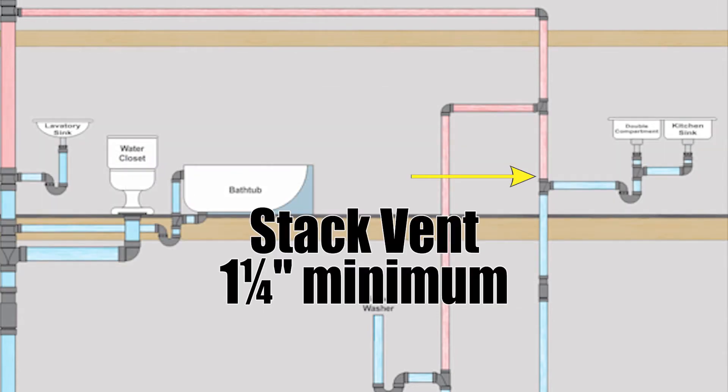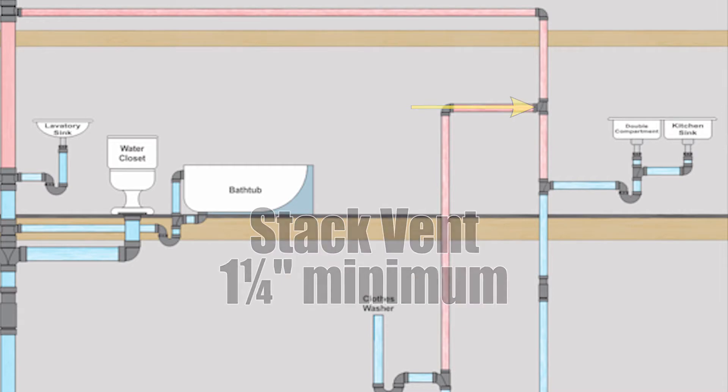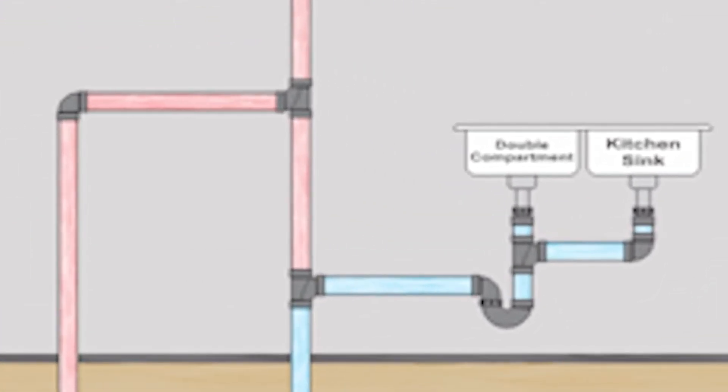Now we'll see that the stack vent goes up and it intersects with the individual vent right there with the TY. There's a couple things we need to talk about right there. The first thing I want to point out is the orientation of the TY. Notice how it looks like it's upside down. Well that's how we put it in for venting because the general flow of air is going up through the terminal which is the part that pierces the roof.